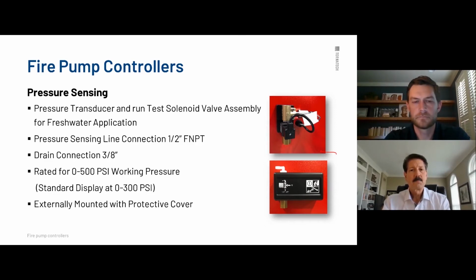And pointing this out, since it's mounted on the bottom left side of the controller, externally mounted wetted parts is actually a huge safety feature. So any facility that has OSHA riding over itself as far as safety concerns would see that as a huge safety advantage, because the one thing you don't want to have is mixing potential water or leakage within a controller, the electrical controller itself, because water and electricity do not mix. And water is a conductive fluid. So that's a huge advantage right there.